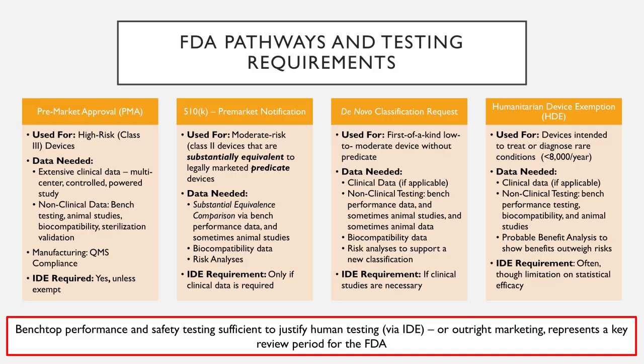And you almost always have to do an IDE that's going to give you the permission to do the clinical trials in the first place. And it's only in very select cases, where you still qualify as a high-risk device but can be exempt from clinical trials for any number of justifications, that you might not need that.